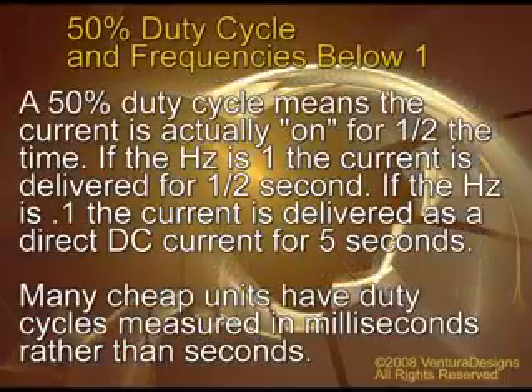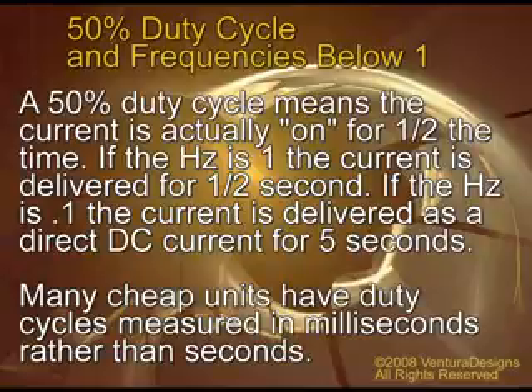The unit must have a 50% duty cycle and frequencies below 1. A 50% duty cycle means the current is actually on for 1/2 the time. If the hertz is 1, the current is delivered for 1/2 second. If the hertz is 0.1, the current is delivered as a direct DC current for 5 seconds. Many cheap units have duty cycles measured in milliseconds rather than seconds.